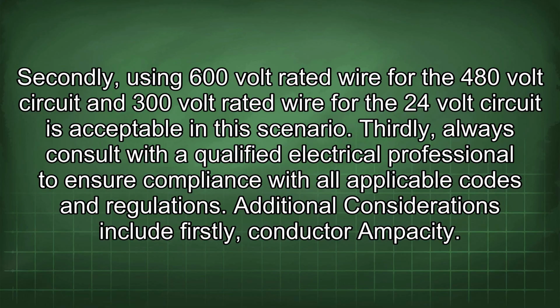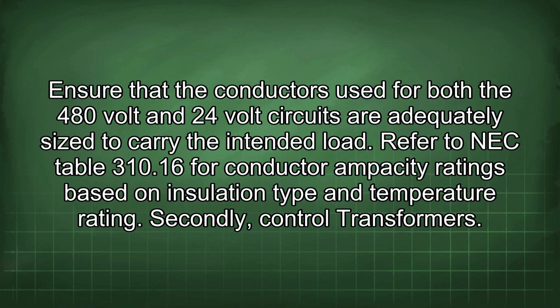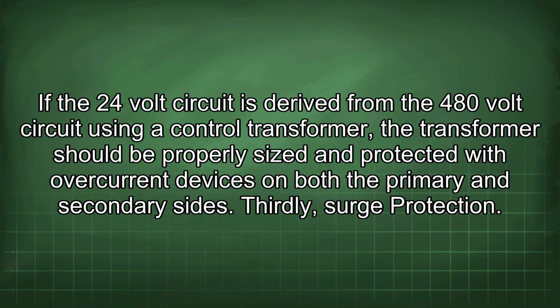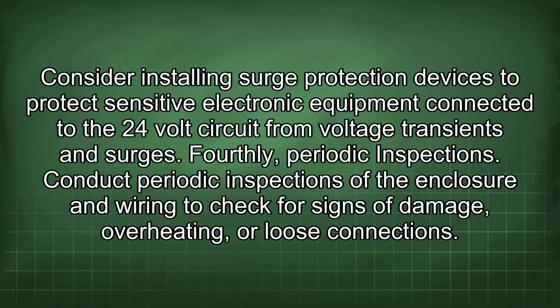Additional considerations include, firstly, conductor ampacity. Ensure that the conductors used for both the 480-volt and 24-volt circuits are adequately sized to carry the intended load. Refer to NEC Table 310.16 for conductor ampacity ratings based on insulation type and temperature rating. Secondly, control transformers. If the 24-volt circuit is derived from the 480-volt circuit using a control transformer, the transformer should be properly sized and protected with overcurrent devices on both the primary and secondary sides. Thirdly, surge protection.